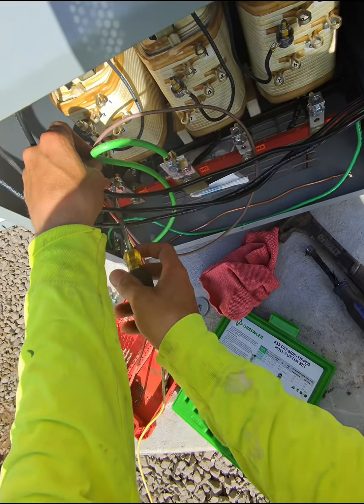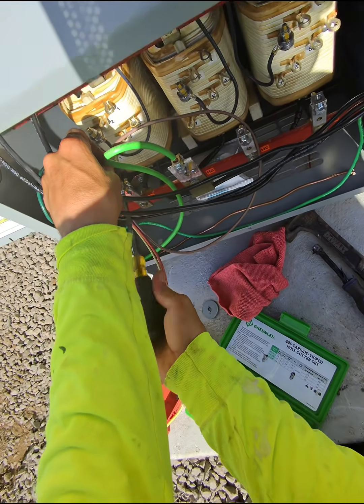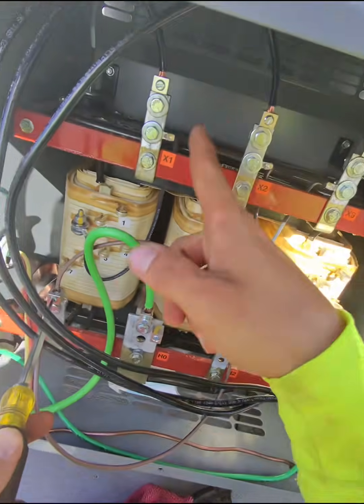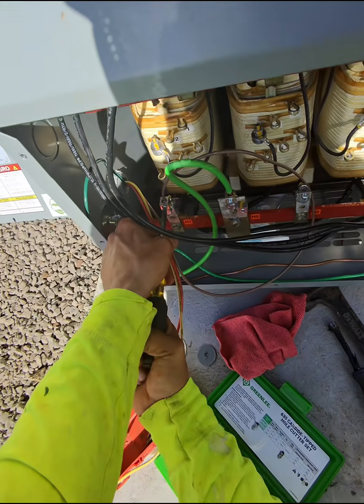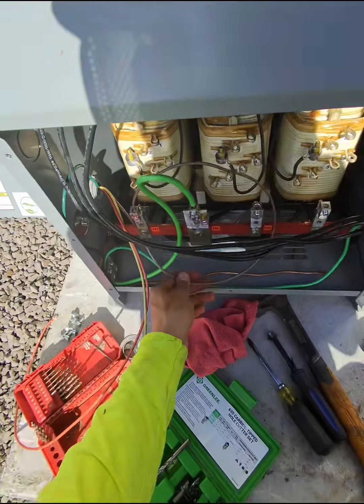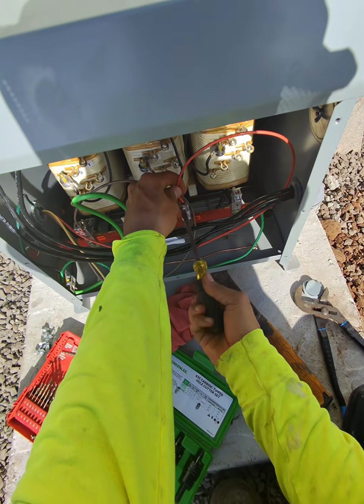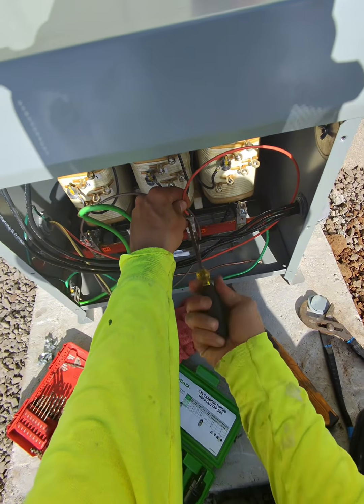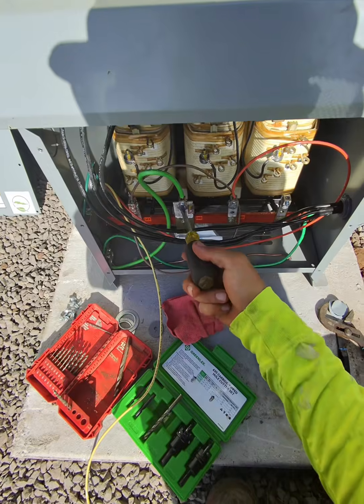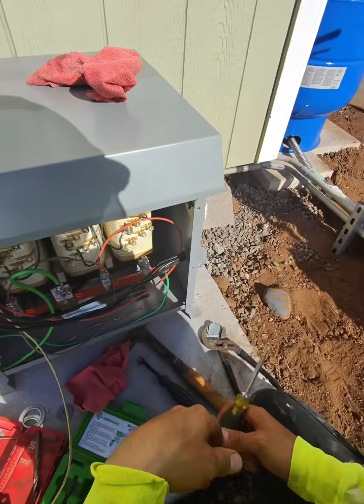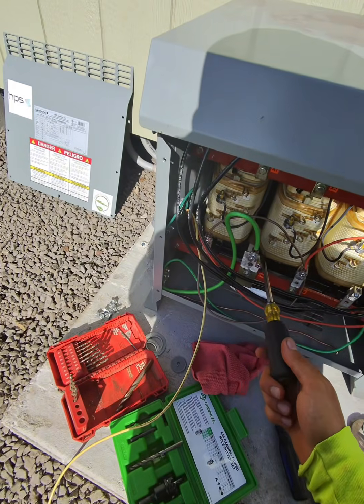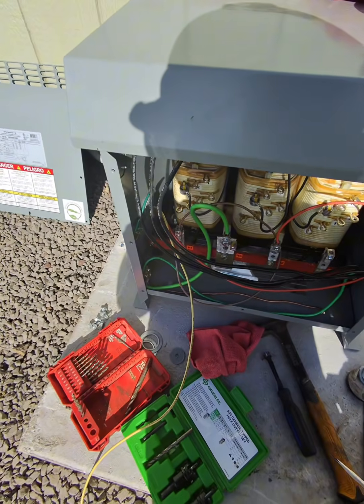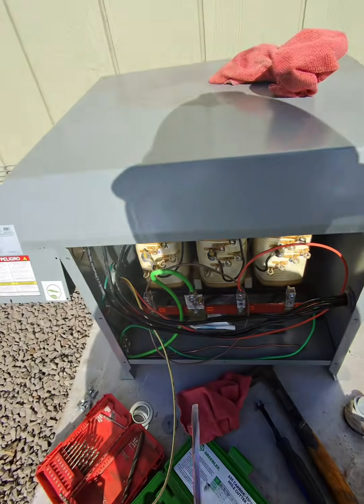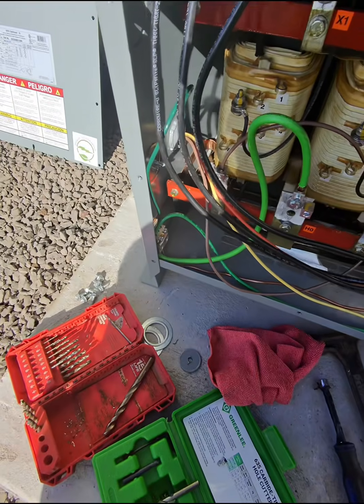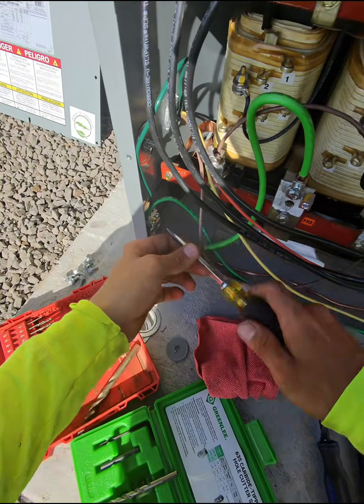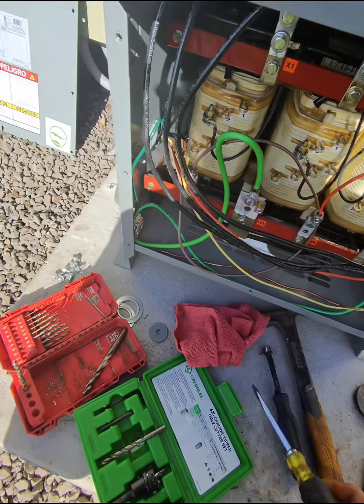Actually using this transformer as a step-up transformer. So we have 208 3-phase coming in on the X side here. It's a delta configuration transformer, and the secondary is a Y configuration, a 480 volt Y. The center tap here, even though we're not bringing a neutral out because all we need it for is this well load right here, I still have it bonded using a bonding jumper to the equipment ground and electrode grounding system. Should be good to go. I'm going to leave this open so that the inspector can see it in all of its glory when he comes over here. Let's move on to some other issues.